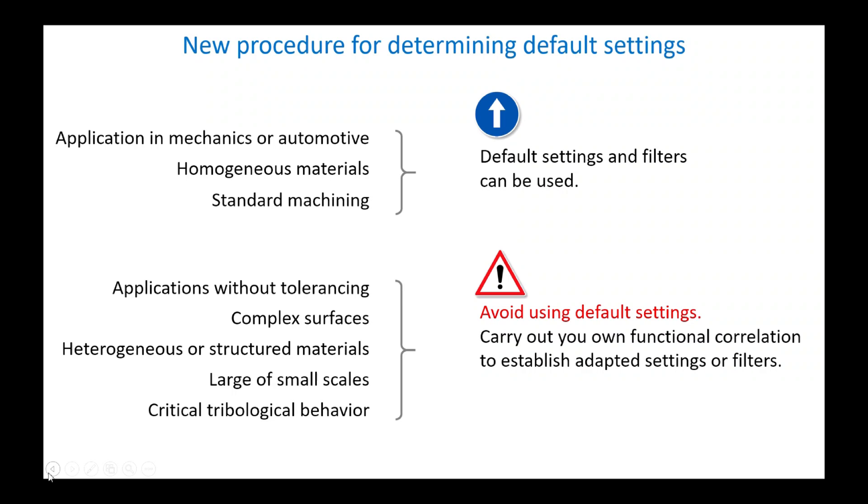On this subject, at DigitalSurf, we believe that the different settings, and in particular the cutoff, should be chosen deliberately depending on the application, materials, and/or manufacturing processes. This is the condition for obtaining a good functional correlation between the calculated parameters and the monitored functions. Setting them by default hides their significance from the eyes of the metrologist and leads many users to use them without asking any questions.